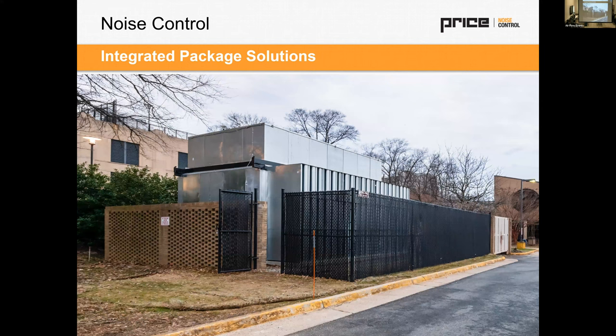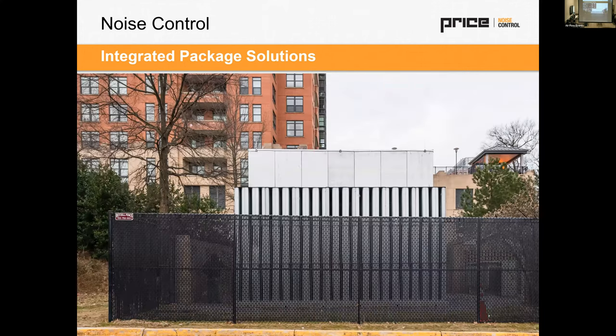This is in Virginia. What happened was this property owner in behind installed a very loud chiller directly in the backyard of a high-end condo, turned the thing on and then didn't think of the noise. Immediately they had lawsuits being filed from the condo board onto the owner. So we designed this acoustic abatement enclosure with silencers and panels. That's a unique look at how to mitigate the noise from a chiller. You can see how close the condo is there.